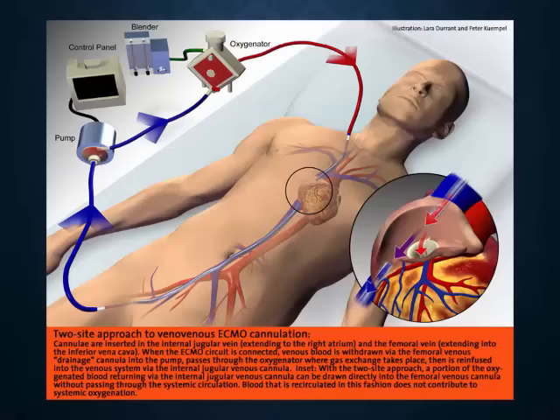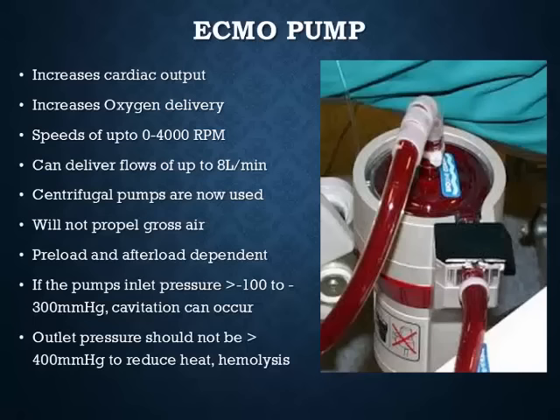This is a brief diagram of how it typically flows. If you've got an access cannula in the IVC through the femoral approach, blood flows from there to the pump, through the pump, through the oxygenator — where you're titrating the gases — and from the oxygenator, oxygenated blood goes back into the SVC.